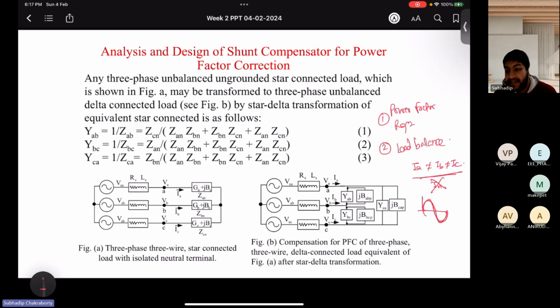However, it contains negative sequence currents because there is load unbalance. That may be possible in these kinds of systems. You may connect one load between some two phases, and on one phase you may not connect any load. So inherently there are chances of load unbalance, which may lead to negative sequence components, which need to be compensated with the help of compensators. That's why load balancing is still an issue for three-phase, three-wire systems.